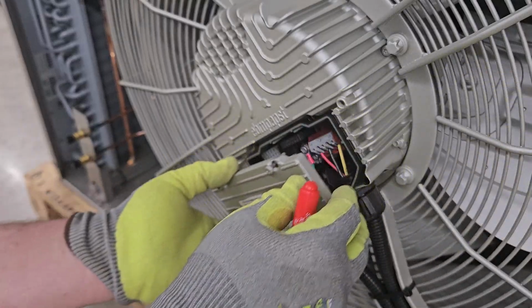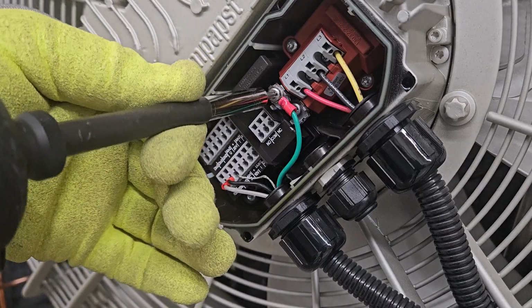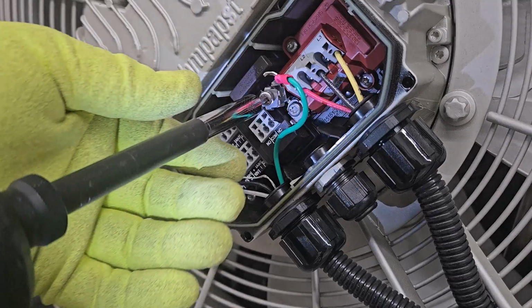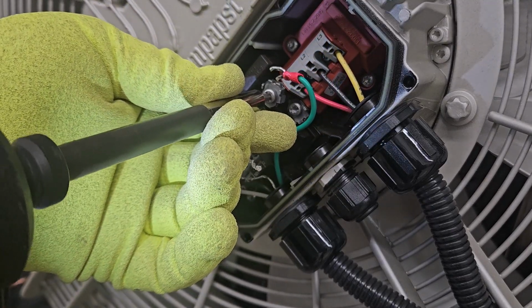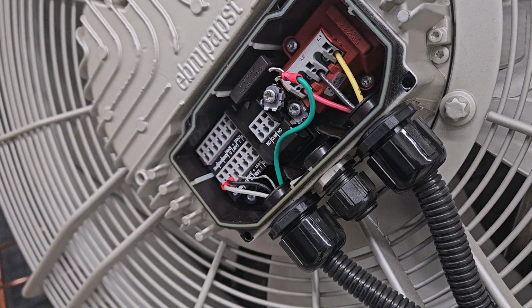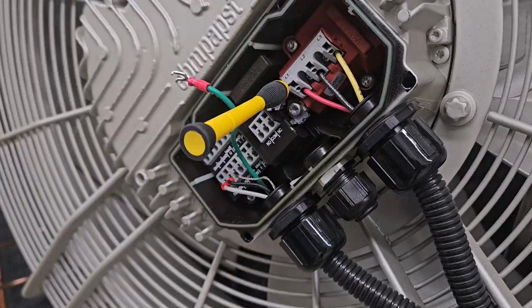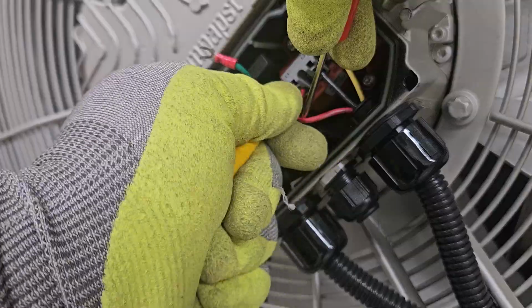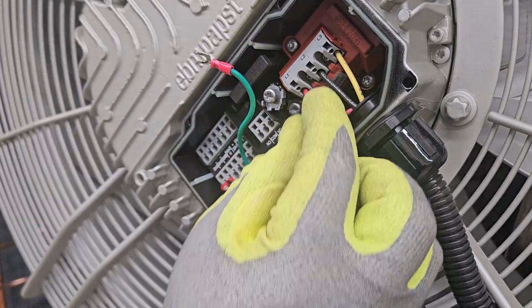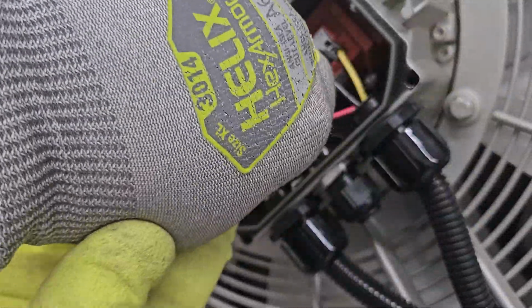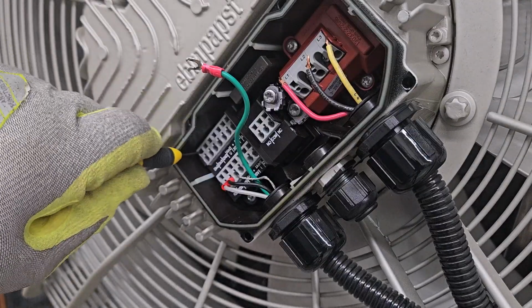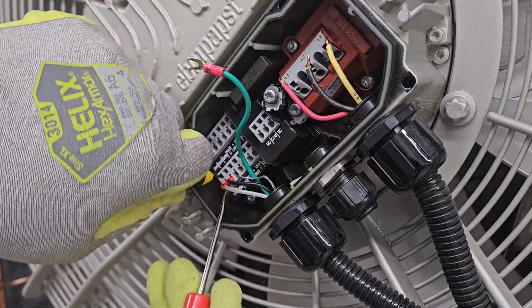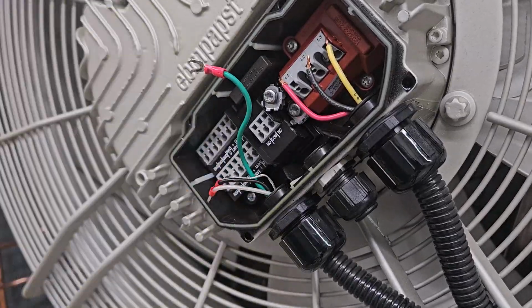The next step will be removing the grounding wire, communication wire, and the high voltage power wires from the motor. Make sure to note the correct terminals that the wires were attached to when replacing with the new motor. This would be a great place to take a picture as you begin to disassemble the wiring harness. The wires can be tricky to get out of the terminals as they compress the wires between two metal prongs. A small screwdriver inserted into the release port should do the trick.